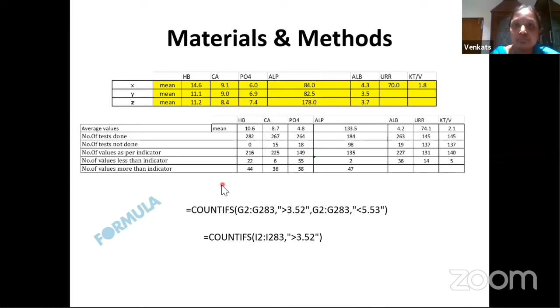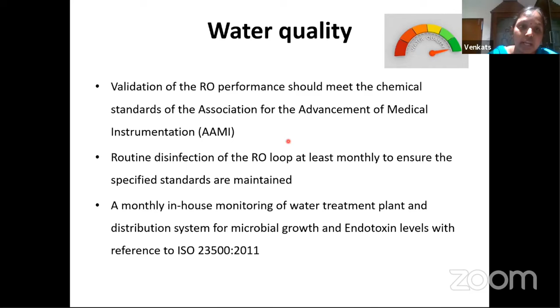Coming to water quality, there are a few things which have to be checked. Routine disinfection has to be done on a monthly basis. And as I told, we are sending monthly samples for endotoxin count and microbial count. The samples have to be sent before disinfection. And once in a year we send samples for complete chemical analysis of RO water, what we get as a product. And we check whether they are falling in the normal range as per AAMI or ISO guidelines.